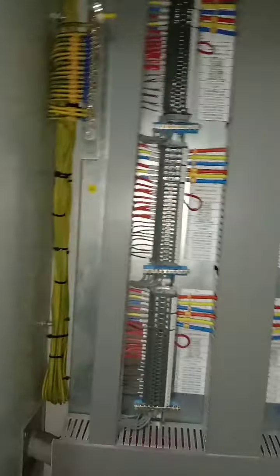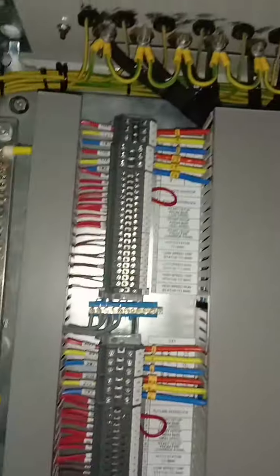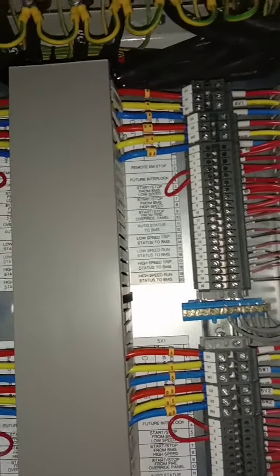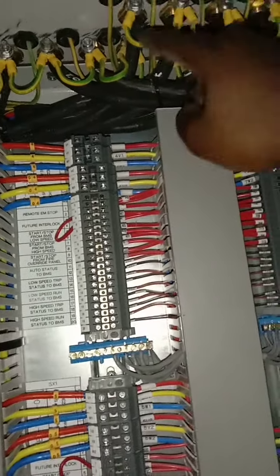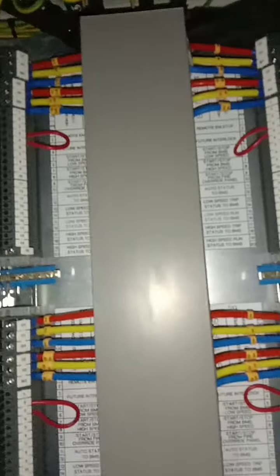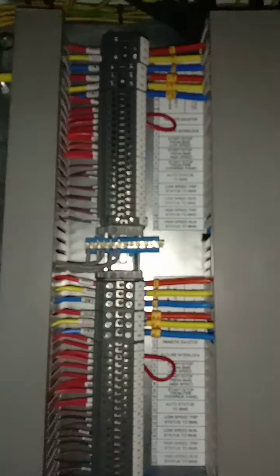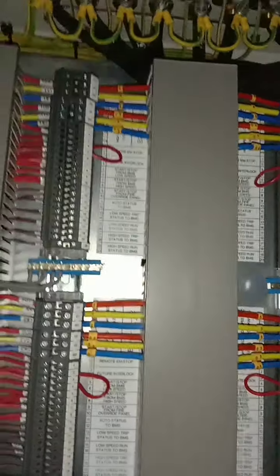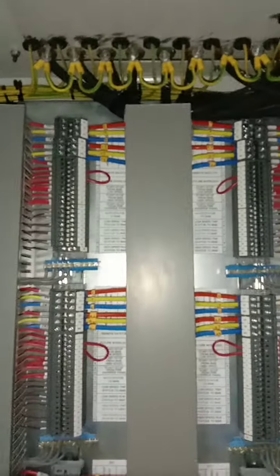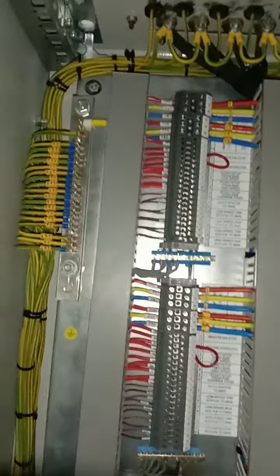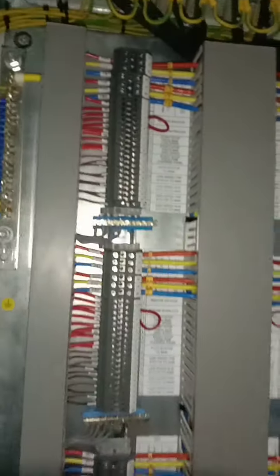As you can see, everything is being connected, and at the top here we have bonding, which is done as well. The bonding is connected to the earth link of the gland, the copper gland. As you can see, we've done the looping all together and brought it to the earth bar, so everything is bonded. Why do we bond this? We bond this so that it will be connected to the armoring part of the cable, because this is an armored cable which has strips of armor inside. So when we do this bonding, we automatically bond the armoring part of the cable as well.